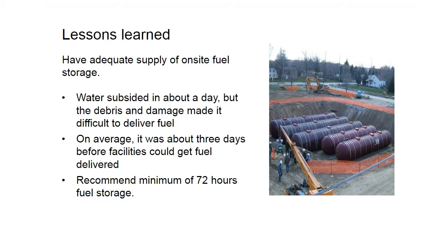Another one that we saw a lot of is, we talked about fuel capacity and having an adequate fuel supply. Even though the water did subside in a day or two, all the debris made it very difficult to get to certain areas. So having that extra fuel on site, the ability to have 72 hours or so to keep those facilities running. We had facilities running for a week, so really take a look at how much fuel you can have. I know a lot of people say we have contracts in place to get fuel, but if they can't get there, that contract doesn't do a whole lot of good. Another thing we did see was that by the time the fuel got there, it was basically bottom of the barrel. It was really dirty fuel, had a lot of particulates in it. Filters were getting filled up really quick. So having a way to replace filters is a big benefit also.